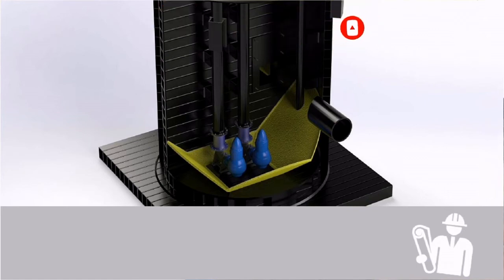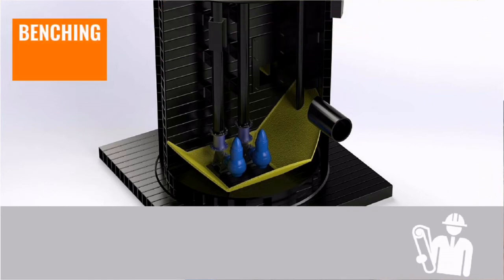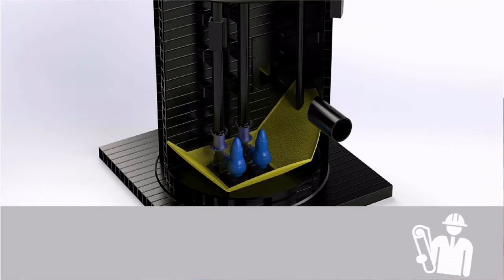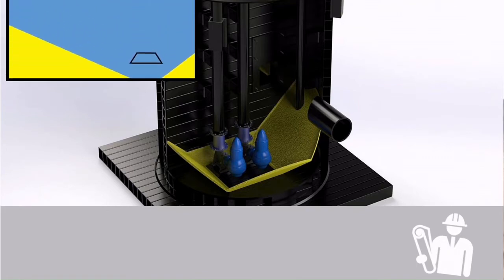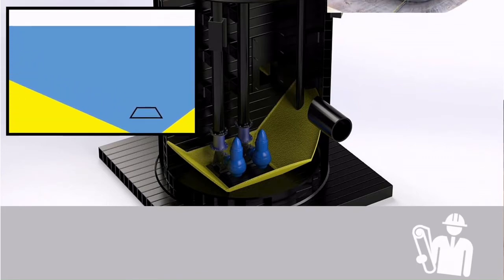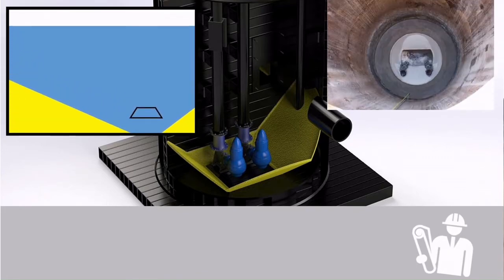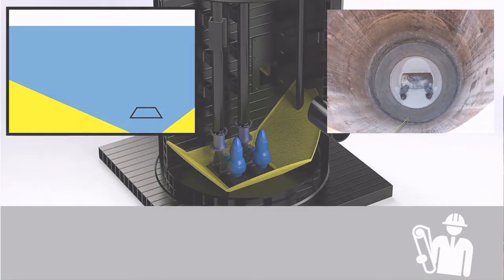First up, benching. If particles are allowed to build up within a wet well, this can cause further issues such as blockages and increased motor strain. By having a steep slope of 45 degrees or higher that leads towards the point that the pump draws liquid, this helps to prevent settlement in the wet well and allows liquid and particles to be removed from the well.